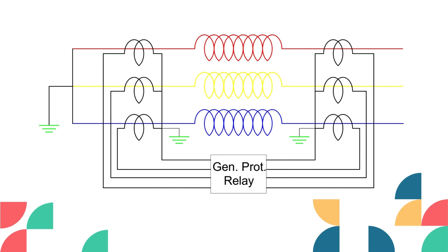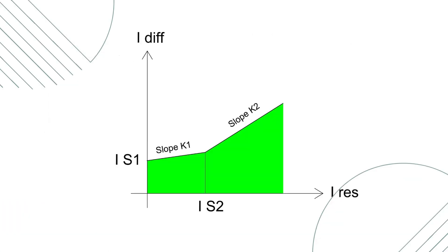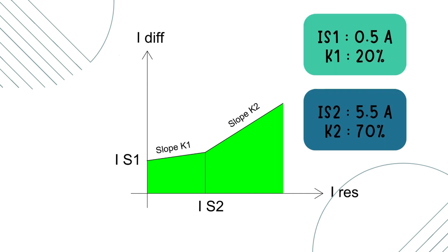Now let's understand how the numerical relay works. The working principle is the same but more simple. All CT cables are connected at specified terminals and we only need to provide the curve details — it will calculate the required setting according to the current value. We provide the values of IS1, K1, IS2, and K2. IS1 is the differential current set at 0.5 ampere, and K1 is the slope set at 20%. To prevent tripping due to external faults, the slope of the relay needs to be increased. As the value of restraining current reaches 5.5 ampere, the slope will be 70%. Nowadays the numerical relay is used everywhere.